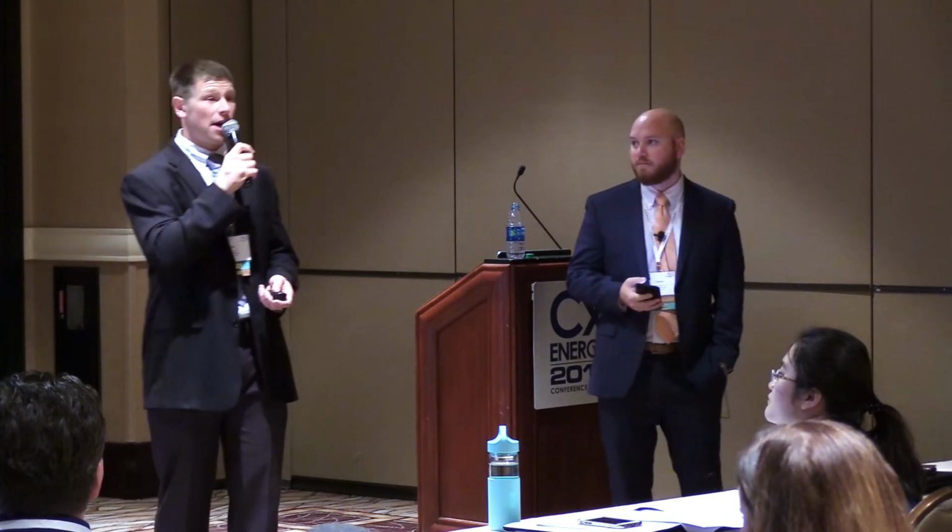And then you have your overall air handling units and your exhaust fans, and we're coming into these labs, and again, it's mixed use, so you've got to be careful on how this is working. One of the labs that we did was 100% outside air, despite the fact that they had big lecture halls and a lot of office and administrative spaces, and they could really use a lot of return air.